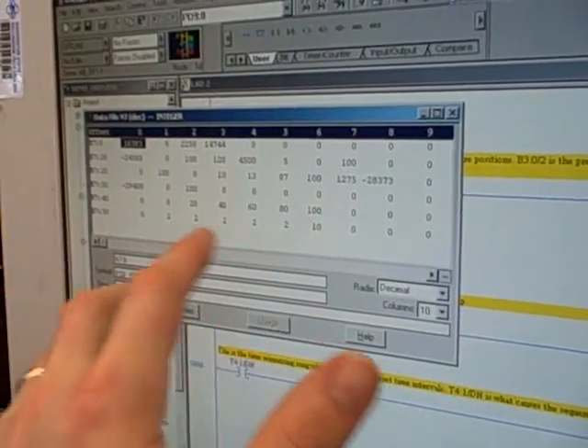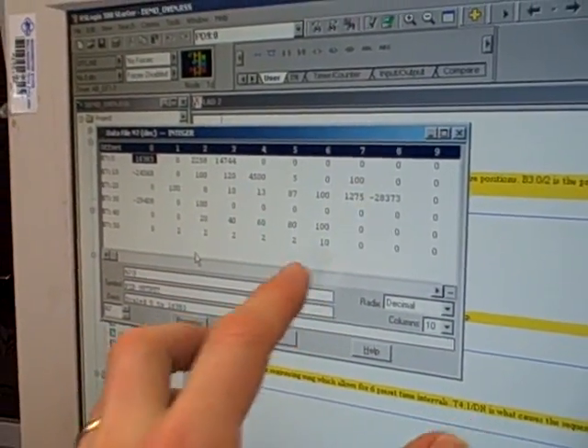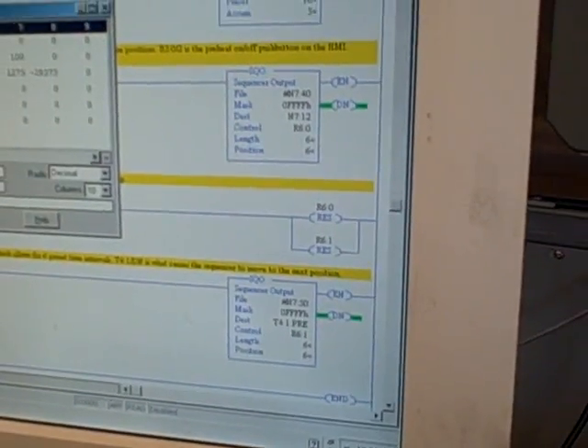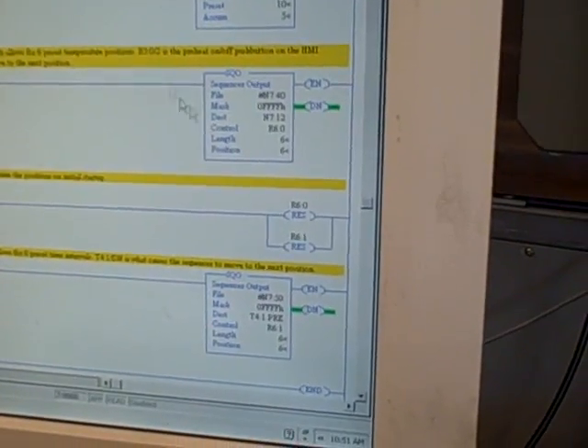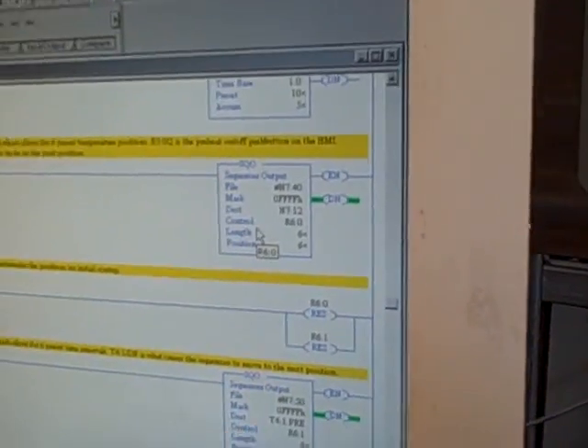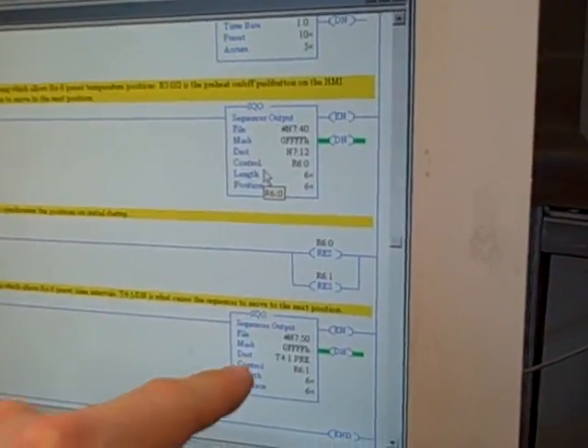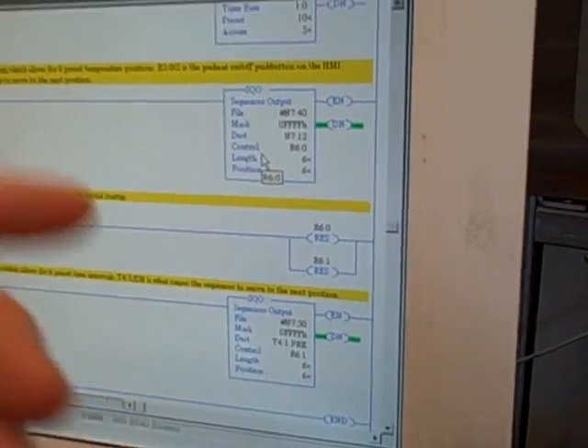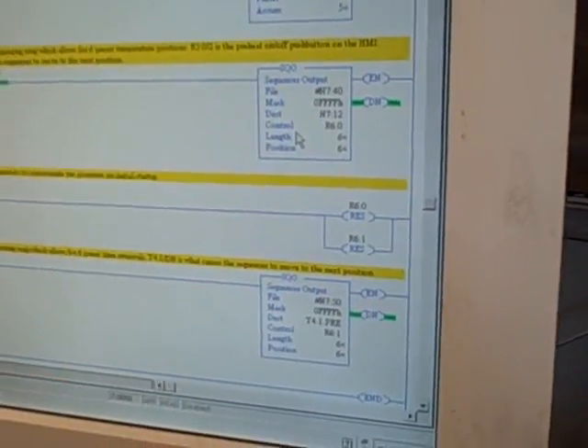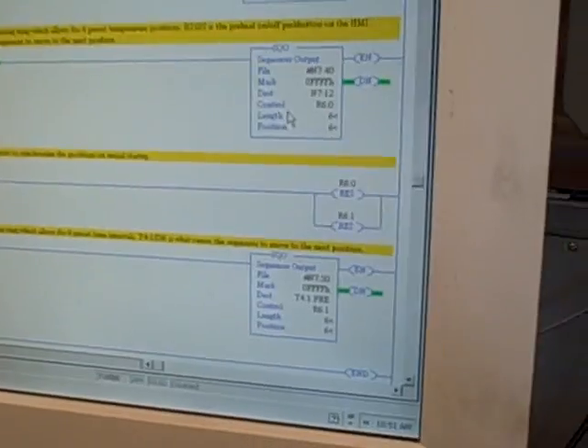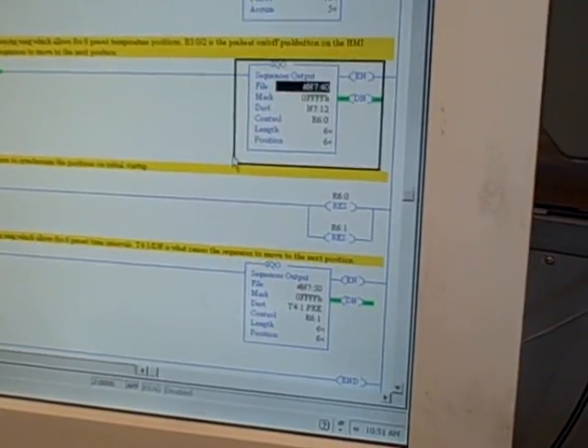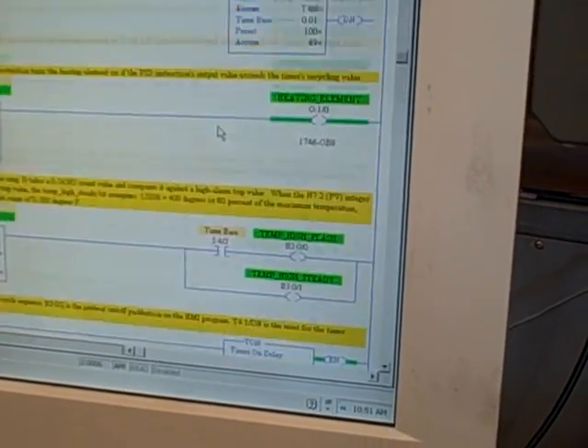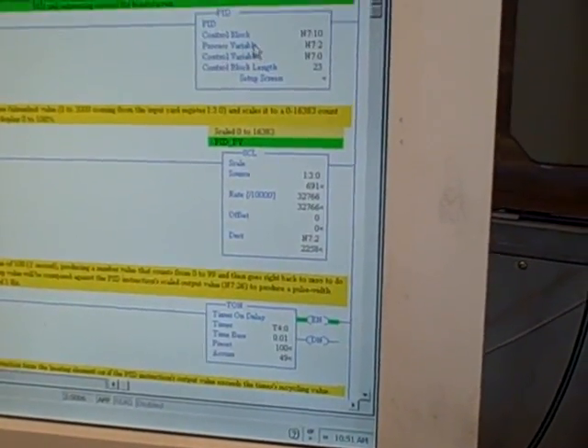Six different set points, six different time durations, and these two sequencer instructions right here, the one at the top and the one at the bottom, are picking off the different set point and time duration values and stepping along and sending those values to the PID instruction where it becomes the set point for the PID control.